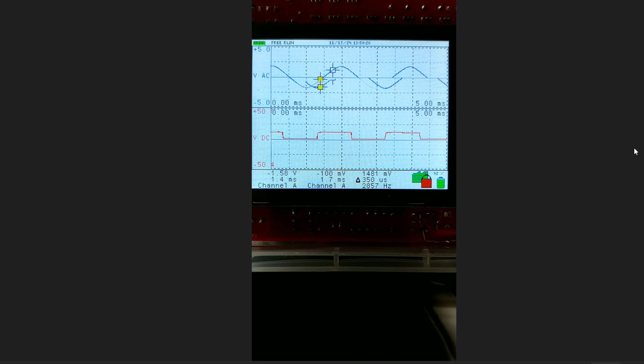Then we move on to channel A instead of the free run as the trigger source. Positive slope. We're going to use the automatic level and hysteresis setting, so we'll look at the data, we'll analyze that data and decide what a good trigger level and threshold is. And I'm going to have 10% pre-trigger, which means that the trigger itself is at about the 10% of the time domain scale, and so you got 10% of the waveform before the trigger and 90% after.